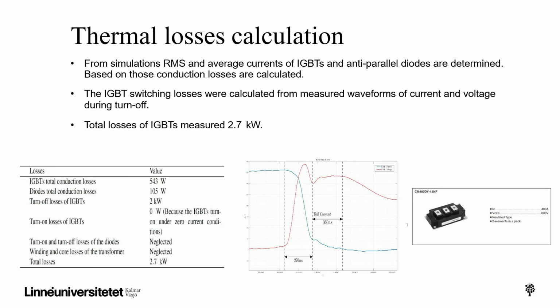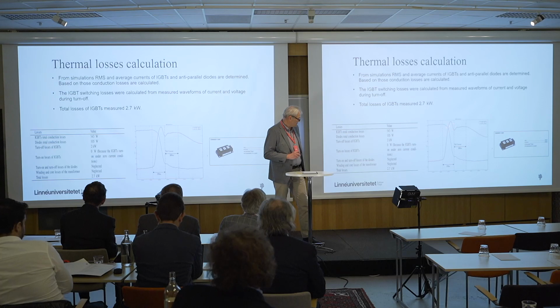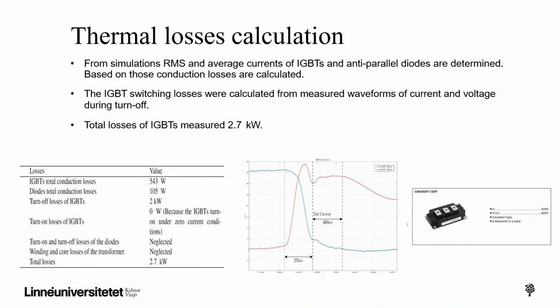And you can see, for example, here, this, which looks like a little bump. That is the impact from the parasitic inductance of the power loop. And this is actually measured on the terminals of the IGBTs. If you go inside here, it is way higher. It's almost clamping to 650 volts. And that is what dominates the switching losses.